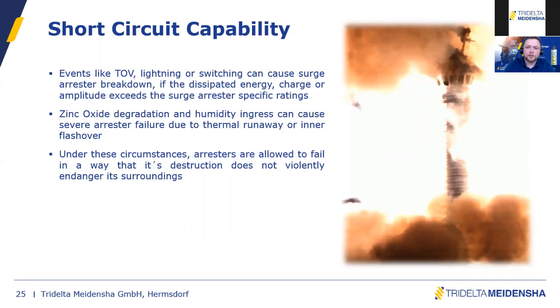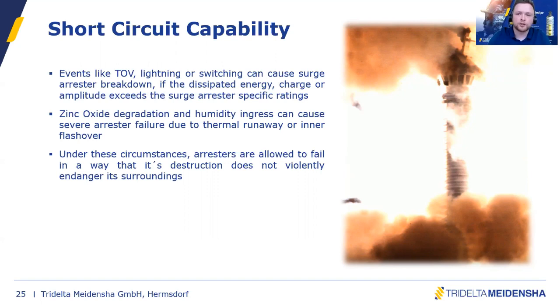Not only the specific line parameters can cause a short circuit on the surge arrestor, but also an aging surge arrestor. If the zinc oxide blocks are affected by an aging process, or if there is a problem with humidity ingress into the surge arrestor, if we have a hollow core surge arrestor, then we can also see arrestor failure due to thermal runaway. So there is continuous heating of the zinc oxide column, and then it gets thermally unstable, and the pressure is rising, and the housing is ejecting the hot air, and the current is flowing across the surge arrestor.